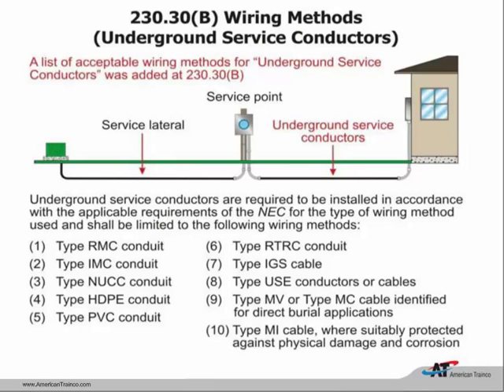Article 230 covers service entrances and provides a list of 10 acceptable underground wiring methods for installing your service. Some methods used for a long time are still included—rigid metal conduit, intermediate metal conduit, PVC—and they added high-density polyethylene and reinforced thermosetting resin conduit. Now there are only 10 methods to install that underground service.